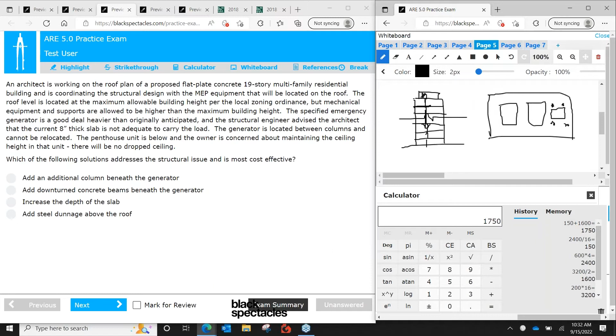Then we have increase the depth of the slab. This is actually the most straightforward solution. If there's too much load, let's just thicken the slab - instead of 8 inches, maybe we need a 10-inch or 12-inch slab right under the penthouse, which would help carry some of that load from the emergency generator. However, again, the owner is concerned about maintaining the ceiling height in that unit, so we can eliminate this option.